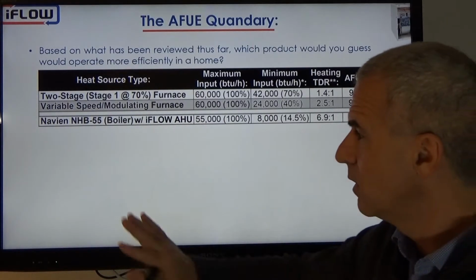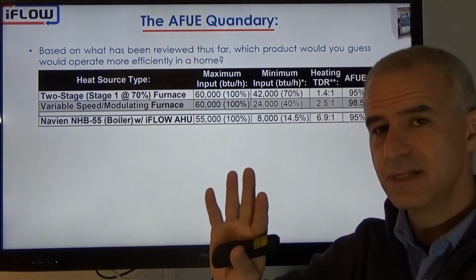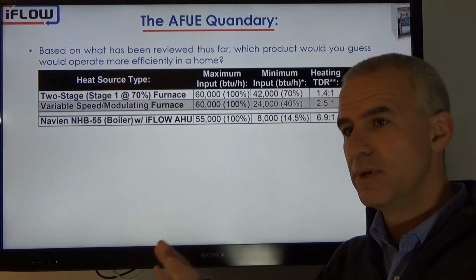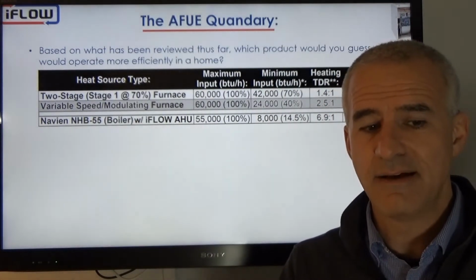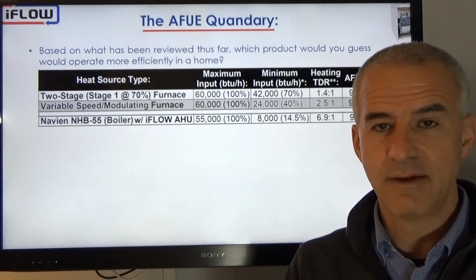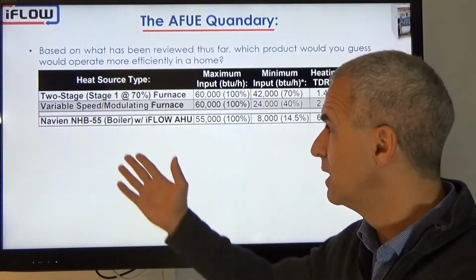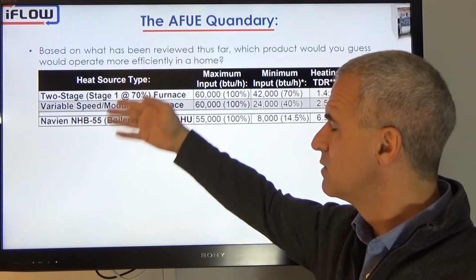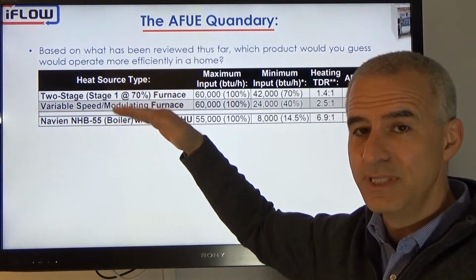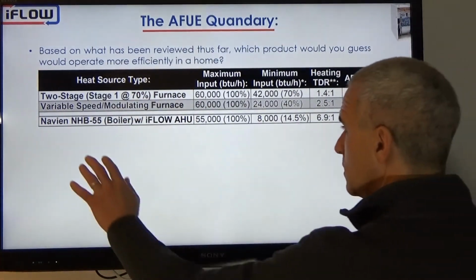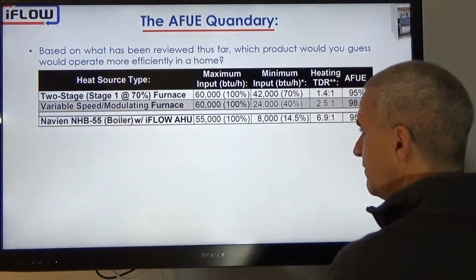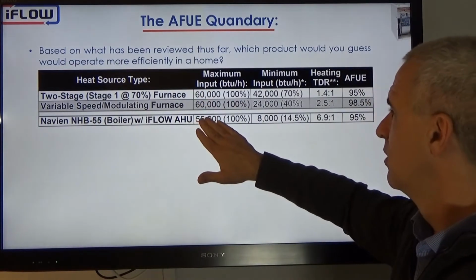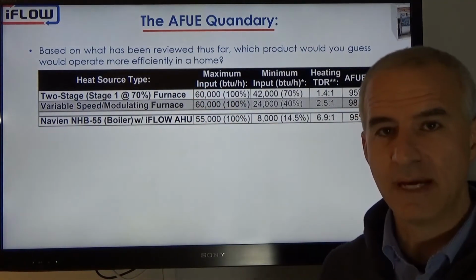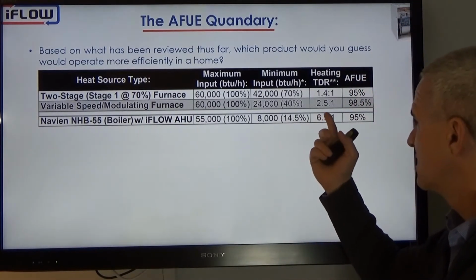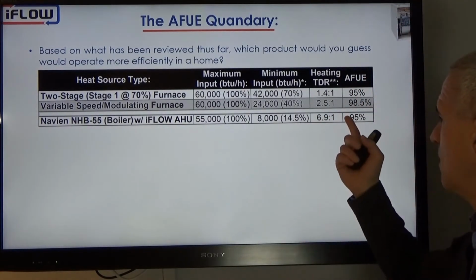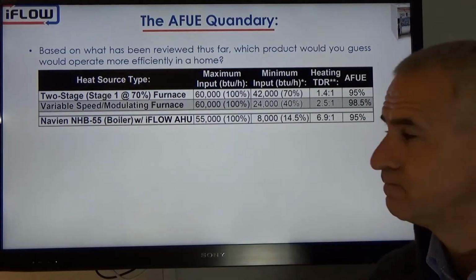Okay? And then we're going to use the NHB 55 just as an example. The only reason I did this is because the tankless units don't have an AFUE rating. They have a UEF rating, but the boiler has an AFUE, so we're comparing AFUE to AFUE. So now we're using the NHB 55, close enough to 60,000 that we could say it's equivalent. It has a minimum input of 8,000 BTUs, giving us a 6.9 to 1 turn down ratio, but it also has an AFUE of 95%.